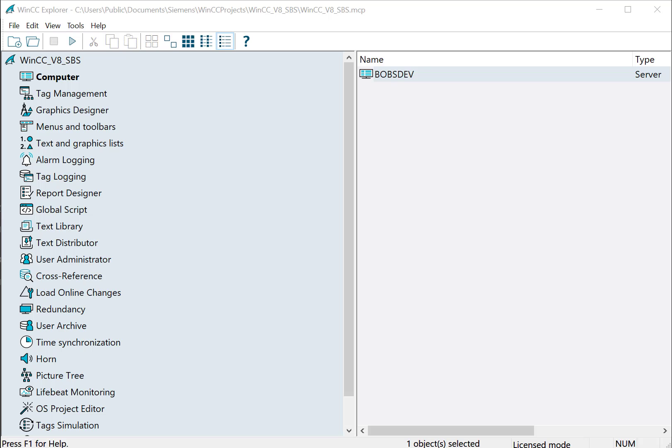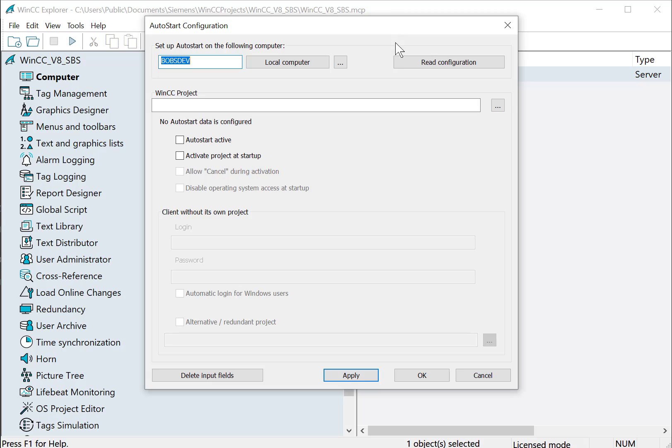And I should be able to click my login screen. If you did forget to do this, you can use Control L. I can log on as my engineer and then I can use Stop RT to deactivate the project. We can also use the Auto Start Configuration app that Siemens provides to automatically start the WinCC project when the computer is rebooted.